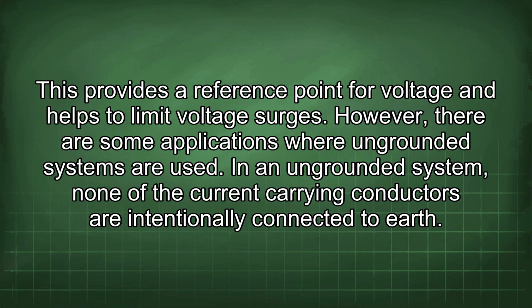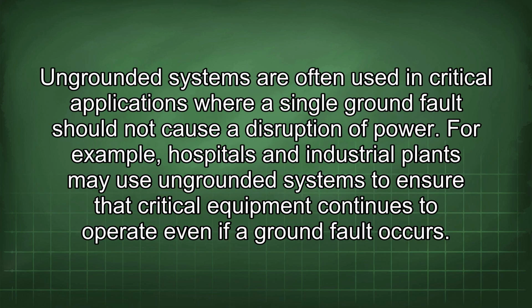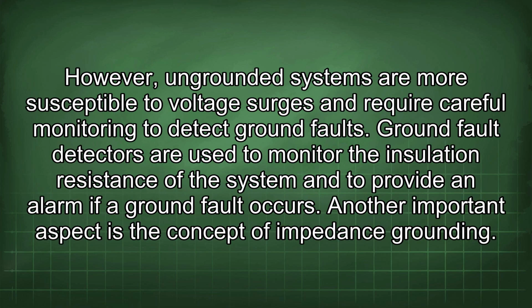However, there are some applications where ungrounded systems are used. In an ungrounded system, none of the current carrying conductors are intentionally connected to earth. Ungrounded systems are often used in critical applications where a single ground fault should not cause a disruption of power. For example, hospitals and industrial plants may use ungrounded systems to ensure that critical equipment continues to operate even if a ground fault occurs. However, ungrounded systems are more susceptible to voltage surges and require careful monitoring to detect ground faults.